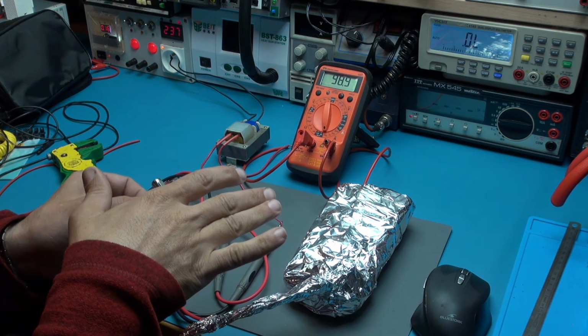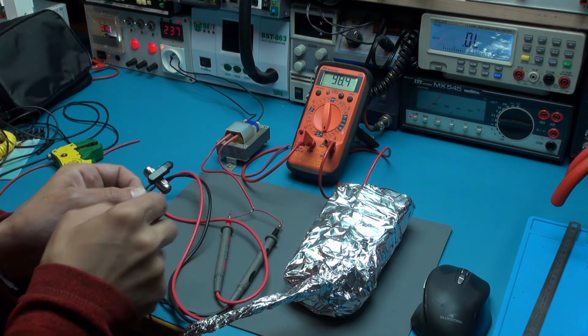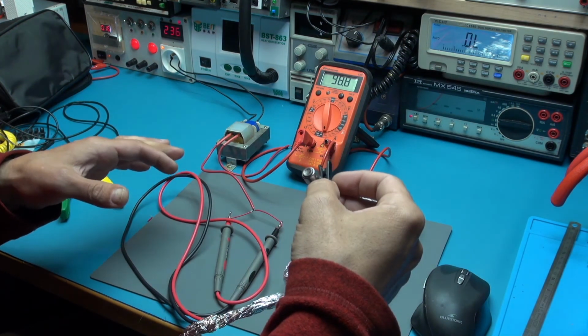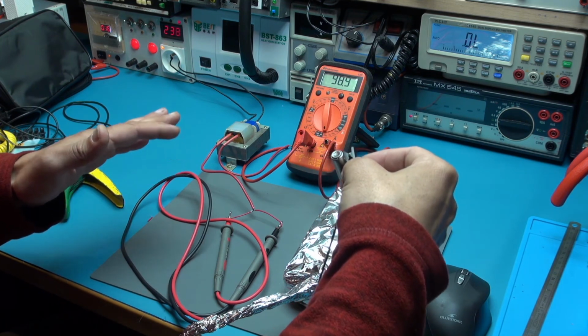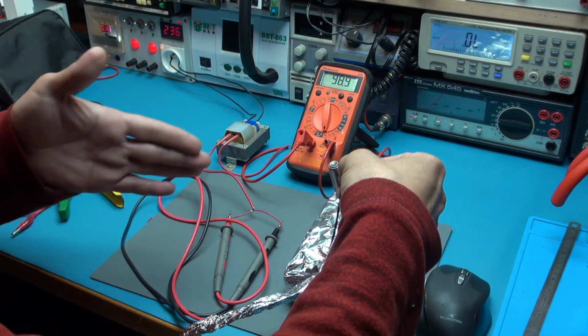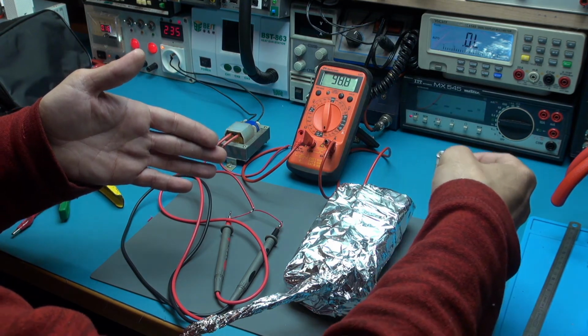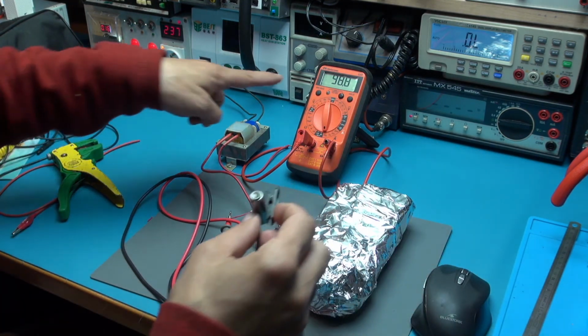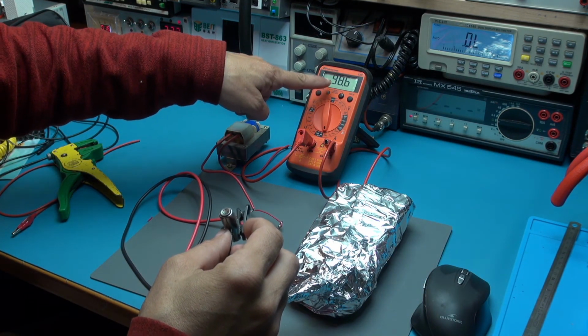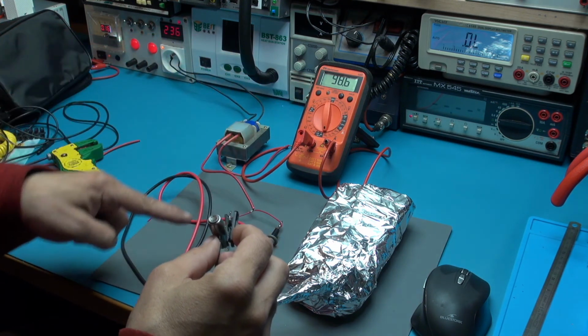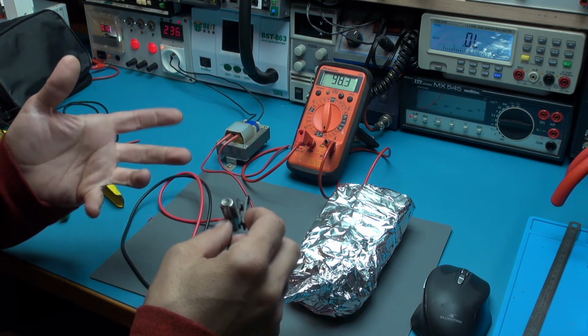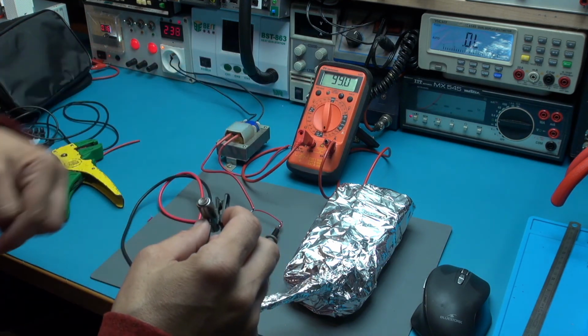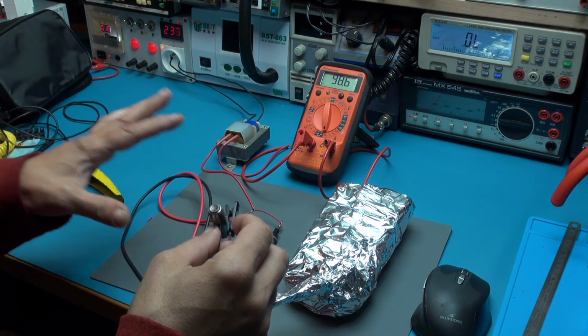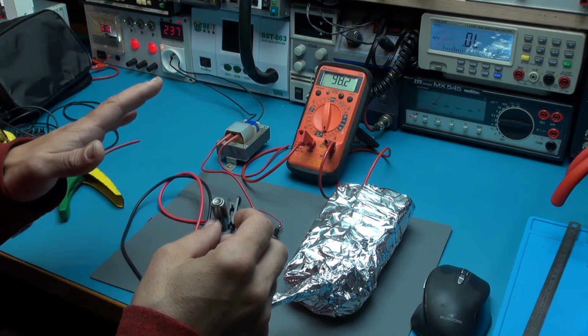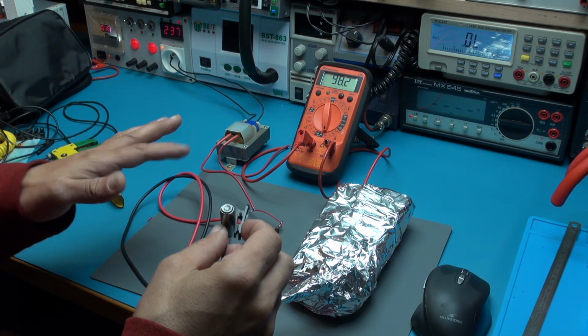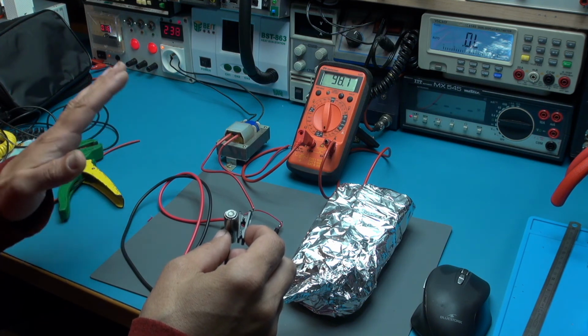Okay. Here it's very dangerous. You absolutely don't want to touch because the voltage is very high. There is no very high current, but the voltage can be very dangerous. So you can see something like 100 microamps. The leak current, electrostatic current, is about this value. And don't forget, this is 4,000 alternating voltage for this test. 4,000 volts.